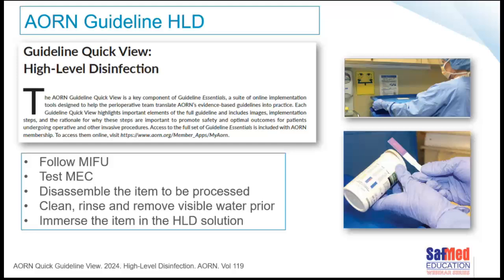The first things that popped out of the guideline, that reminded me of what I wanted us to focus on, were these few points. Remember to follow the manufacturer's instructions for use. Absolutely critical. There are some manufacturers that will state that when you're rinsing the device, you need to rinse it 3 times. Are you doing that? Are you using fresh rinse water? Remembering to test the minimum effective concentration using those test strips.